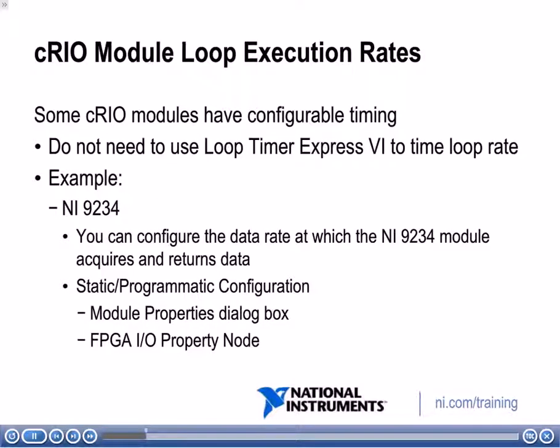You can configure the data rate either using a static dialog box — you can open up a dialog box for the module properties and set the data rate there, which will set the acquisition rate that the module will acquire data at — or you can also do this programmatically using an FPGA IO property node. We'll talk about both of these.